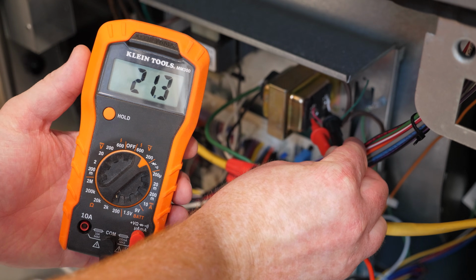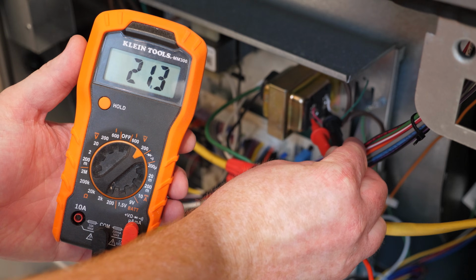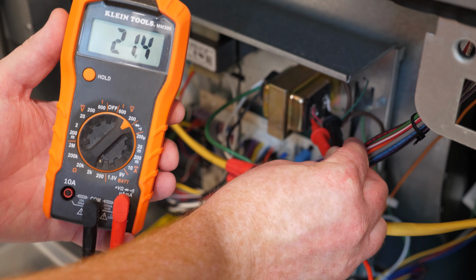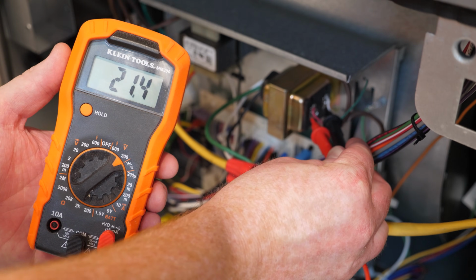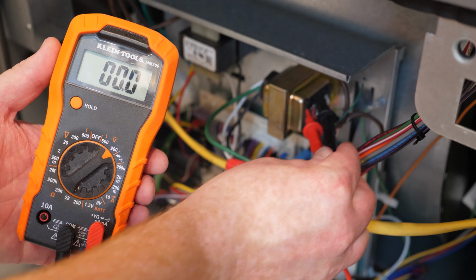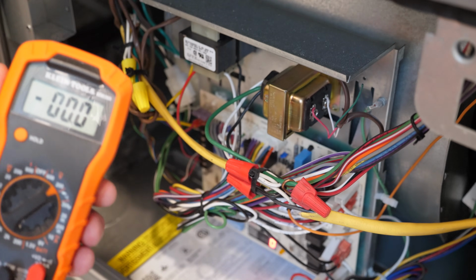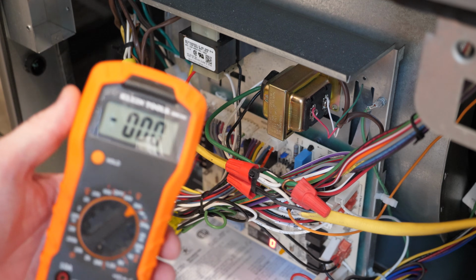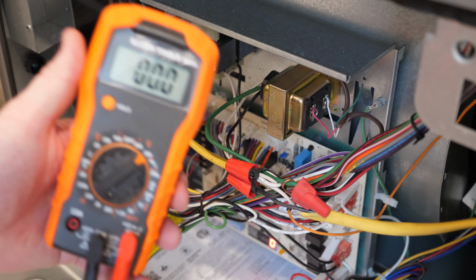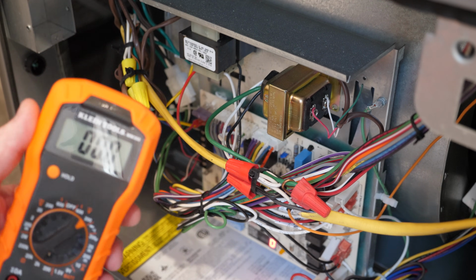All right, and there's our reading. We have 21.3 or 0.4 volts coming from the transformer. So that converted our 120 or 110 volts to 21, and we need a transformer that has 8 to 24 volts. So that means our transformer is compatible with the Nest Doorbell.